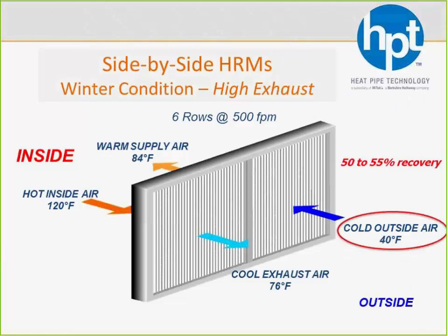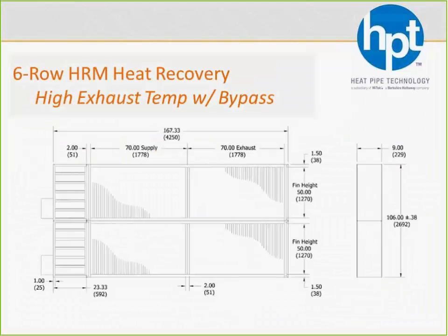Let's now say that it starts warming up outside, so you've got 40 degree air. Well, now instead of 120 degree delta T, we're looking at an 80 degree delta T. We're still recovering about 55% of that, so now instead of heating that up to 66 degrees, we're going to heat it up to 84 degrees. Well, the problem with that is that might be too hot for the space. So what you do to control the temperature on a side-by-side is just add some bypass dampers.